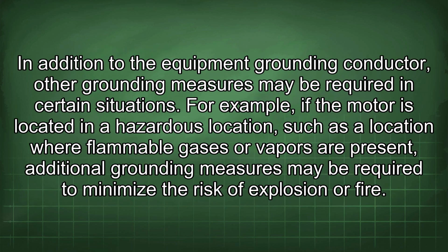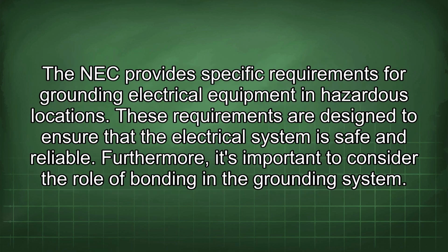In addition to the equipment grounding conductor, other grounding measures may be required in certain situations. For example, if the motor is located in a hazardous location, such as a location where flammable gases or vapors are present, additional grounding measures may be required to minimize the risk of explosion or fire. The NEC provides specific requirements for grounding electrical equipment in hazardous locations. These requirements are designed to ensure that the electrical system is safe and reliable.